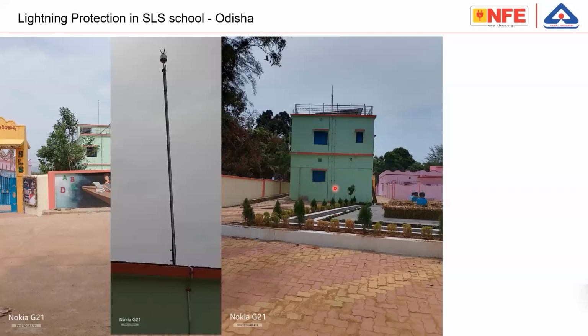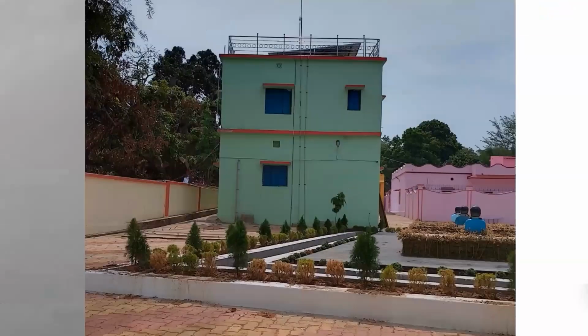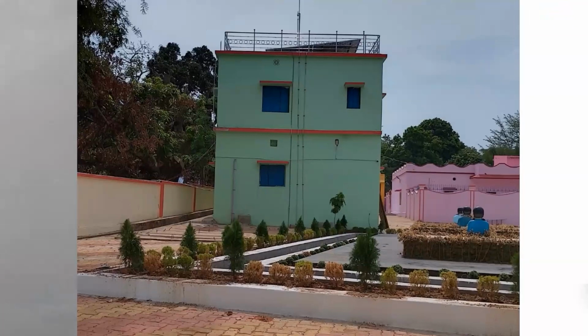A very important subject of lightning protection is that down conductors must be all around the building. If you are routing all the down conductors through one side of the building, that itself is a violation of the standard. Depending upon the size of the building, you need multiple down conductors. It is not like the entire lightning current should flow through one down conductor, which is again dangerous. If you zoom into this picture, the third line from top to bottom, and also the horizontal line in the building, are nothing but electrical conduits through which the electrical wire is running.